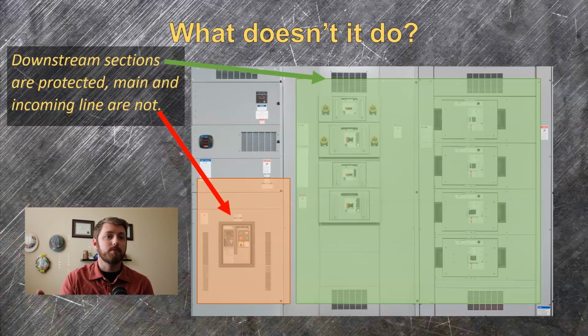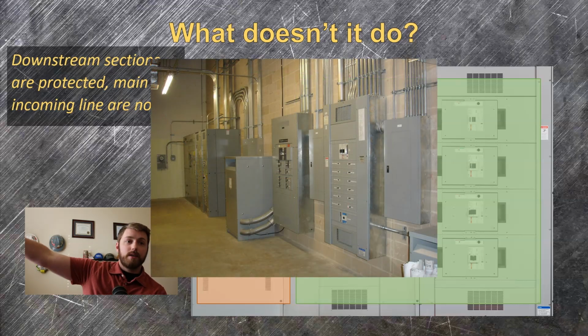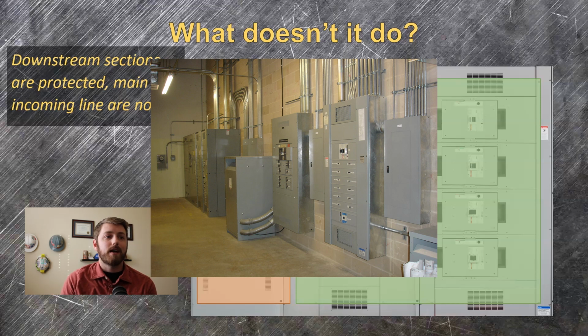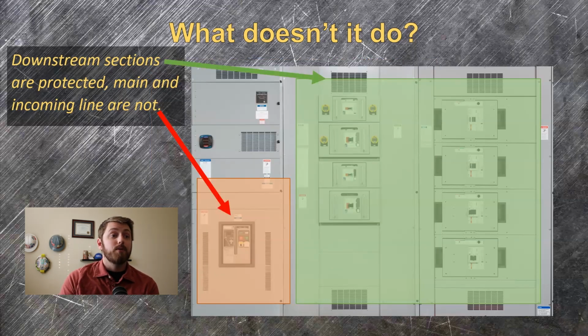An arc flash here will laugh emphatically at the maintenance mode switch as it melts and falls out of the front of the gear. It also doesn't affect anything too far downstream. The arc rating of, say, a lighting panel on the far side of a facility is mostly determined by the size of that little transformer that feeds it, not the upstream protection at the service entrance board. In our example here, maintenance mode is only reasonably effective for reducing the energy inside the service entrance switchgear on the load side or immediately near these feeder breakers that I've got highlighted.